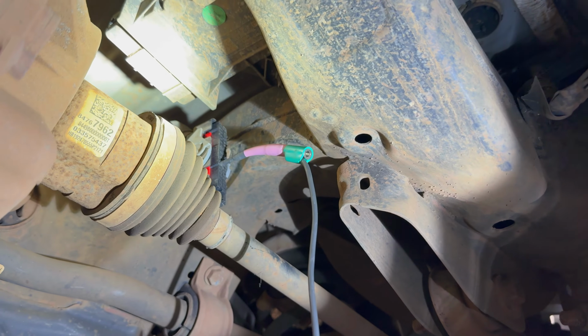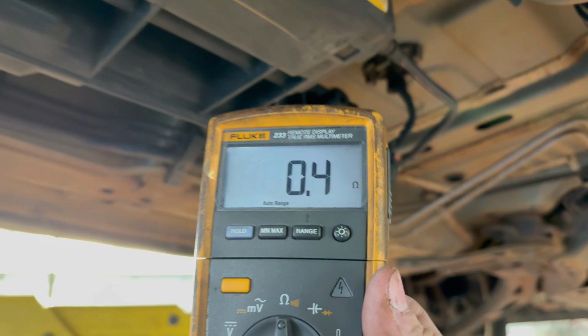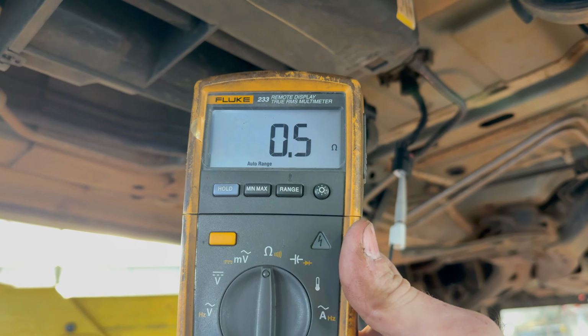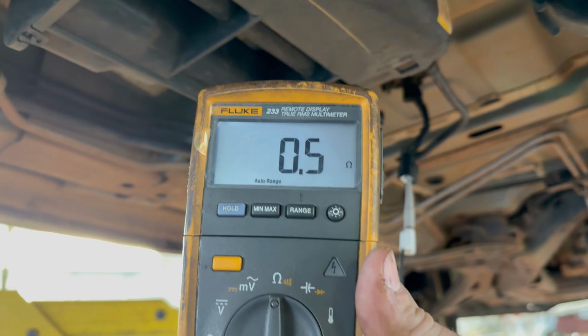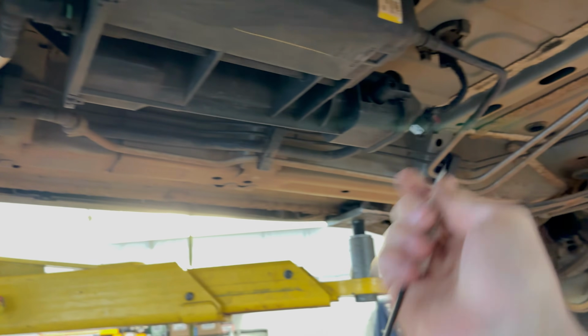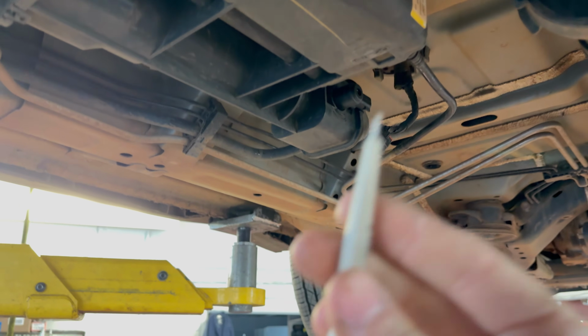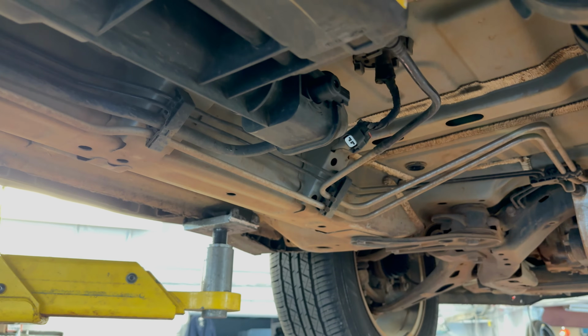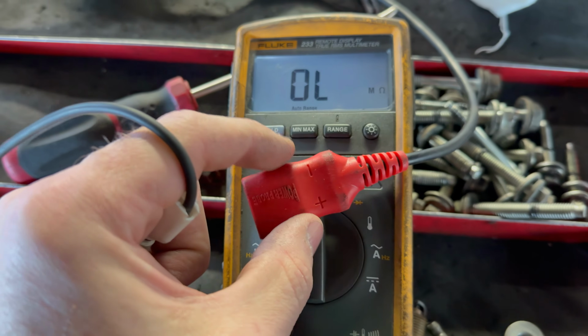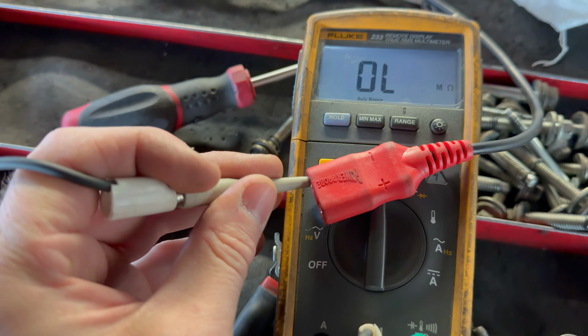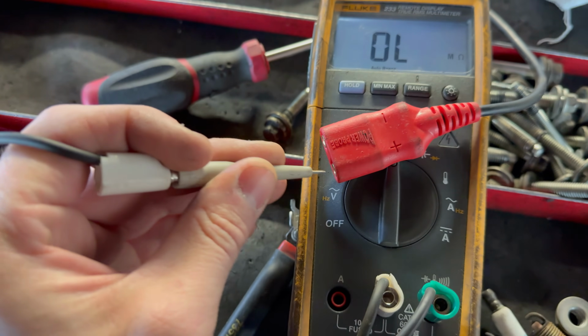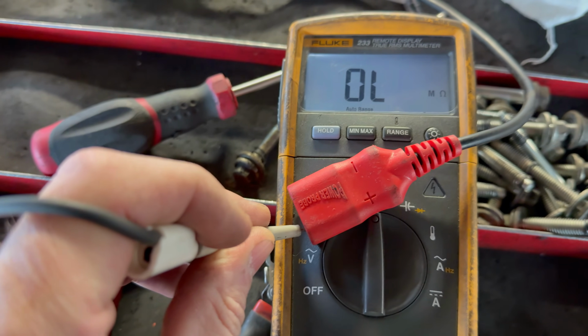Okay, so test from here to here. We've got 0.4, 0.5 ohms, so that's a good continuity test end to end. And then I'd want to check from B plus and ground to verify there's no continuity to ground or B plus. Okay, and I conveniently have the power and ground right here. No continuity to ground, no continuity to power.